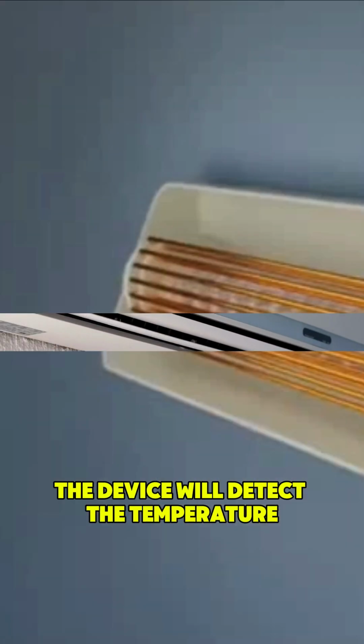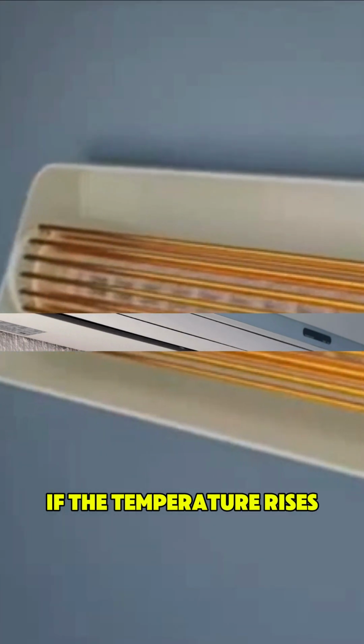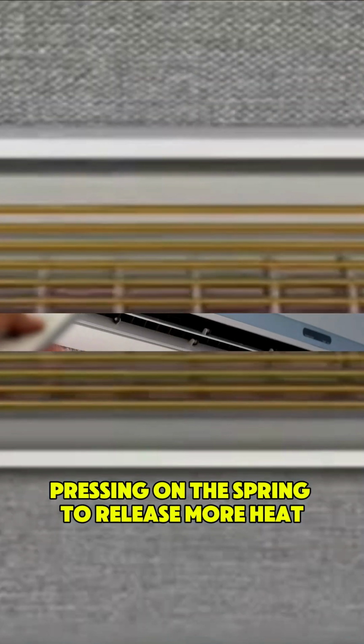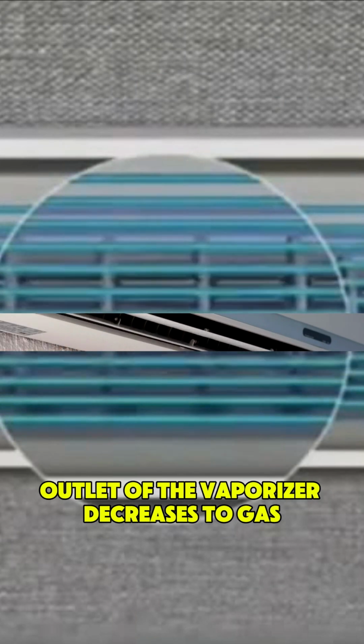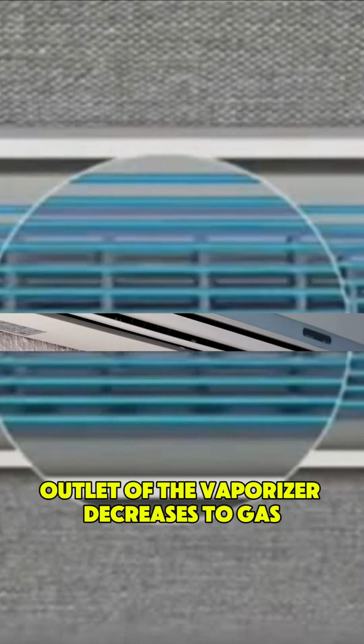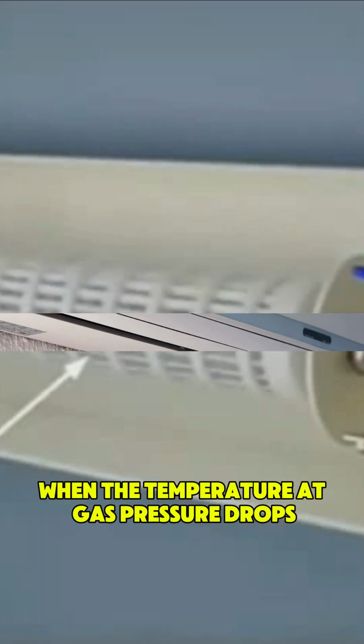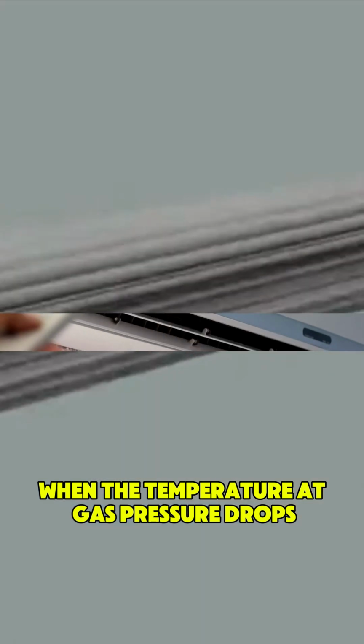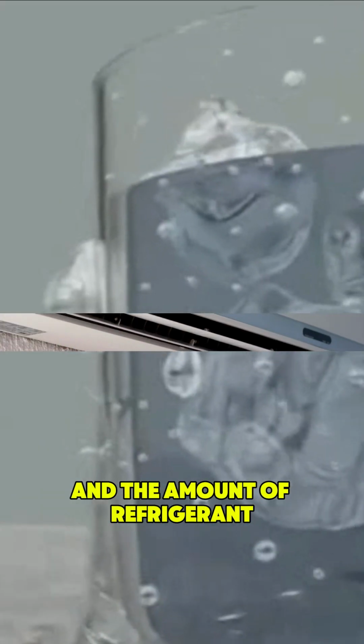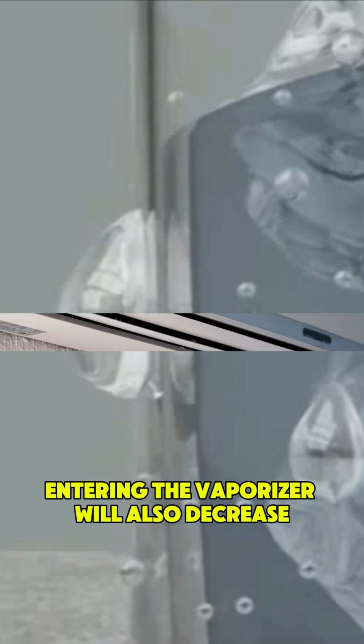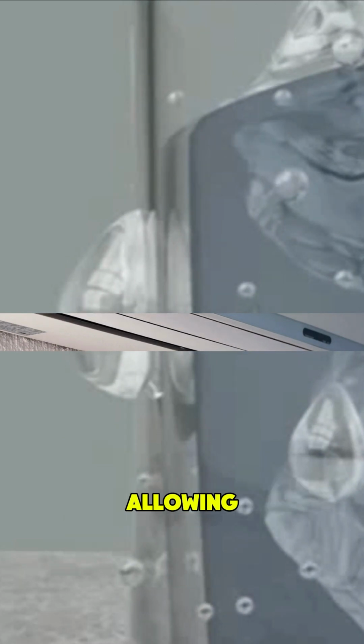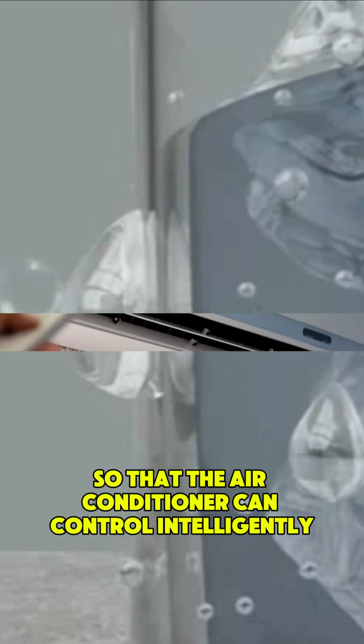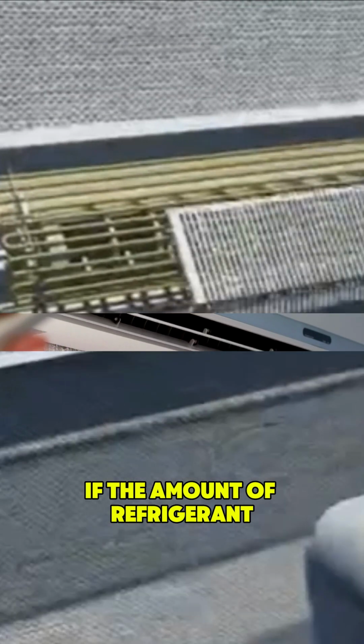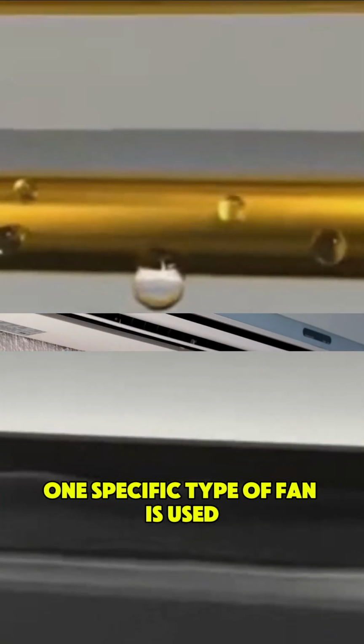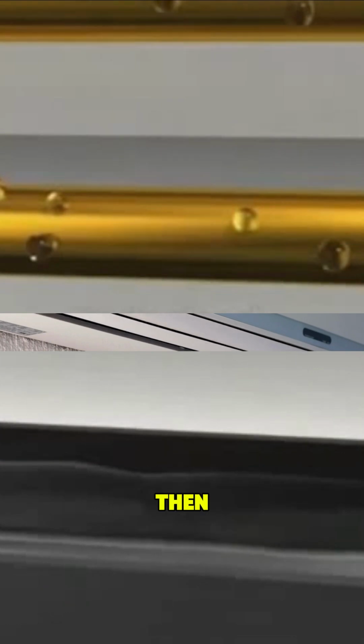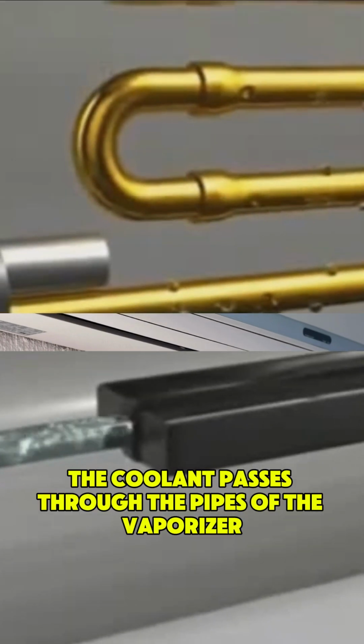The device will detect the temperature. If the temperature rises, it presses on the spring to release more refrigerant, and at the outlet of the vaporizer the gas pressure will increase. When the temperature and gas pressure drop, the amount of refrigerant entering the vaporizer will also decrease, so that the air conditioner can control intelligently if the amount of refrigerant is excessive or insufficient. Then the coolant passes through the pipes of the vaporizer.